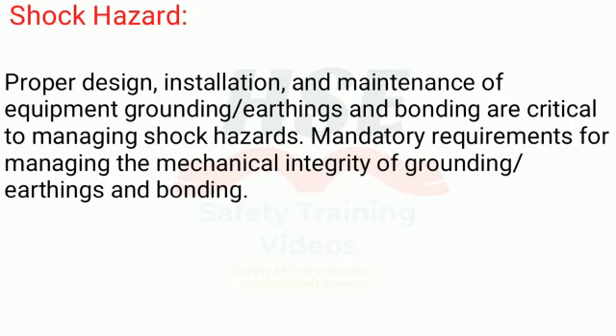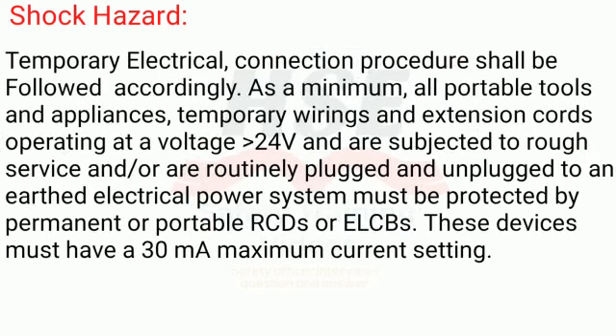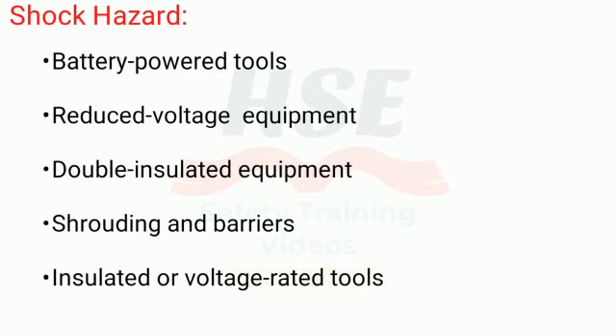Mandatory requirements for managing the mechanical integrity of grounding, earthing and bonding. Temporary electrical connection procedure shall be followed accordingly. As a minimum, all portable tools and appliances, temporary wirings and extension cords operating at a voltage of 24 volts and above, that are subjected to rough service and are routinely plugged and unplugged to an earthed electrical power system, must be protected by permanent or portable RCDs or ELCBs. These devices must have a 30 mA maximum current setting.